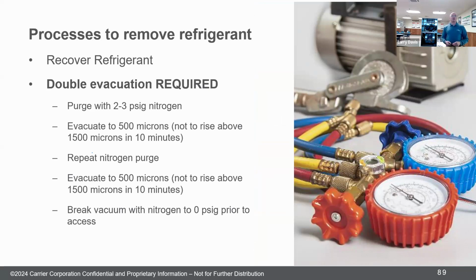Talking about the double evacuation. You recover the refrigerant, and this is required with the 454B systems. It's not a best practice. You have to do this. You double evacuate it. You purge it after you recover it, with 2 to 3 pounds of nitrogen. Release that nitrogen. Evacuate to just 500 microns. My mistake, not to rise above 1,500. That was the number. And then you repeat the nitrogen purge. So it's recover, purge, evacuate again, and then break it to 0 with nitrogen, and then you can open up the system.